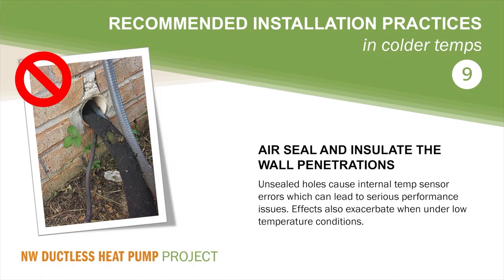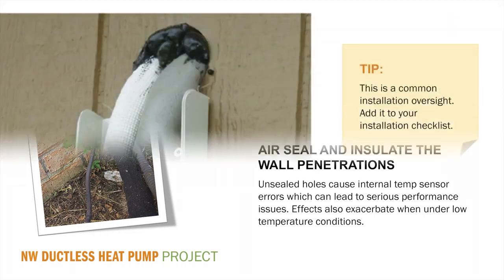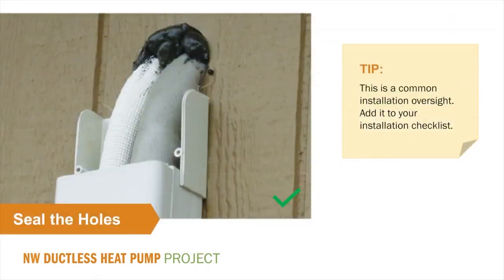The thing about this common installation oversight is that it is hard to identify when it has occurred. The symptoms are not going to be immediately clear to a homeowner and might not be obvious to a service technician. This makes it hard to diagnose. I have learned that if a customer is less than excited about their ductless heat pump and complains that it can't make enough heat when it is below freezing, or that it feels drafty in the room where the ductless indoor unit is located, they may have an unsealed wall penetration.